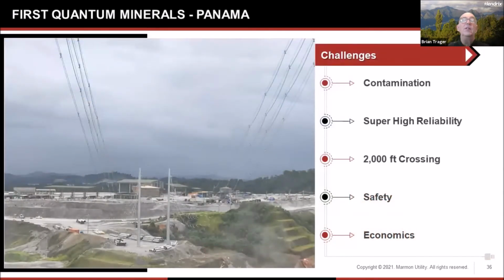We had a lot of challenges in this site. Not only was it virgin jungle we had to go to, there's a lot of wildlife here. There's a lot of rough weather. There's also contamination. Mining sites in particular are contaminated because we have metal products flying around, sitting on the insulators and turning those insulators into conductors. So we really have to have clean insulating surfaces. We've got super high reliability. When you're taking gold out of the ground, you don't want to take a break.